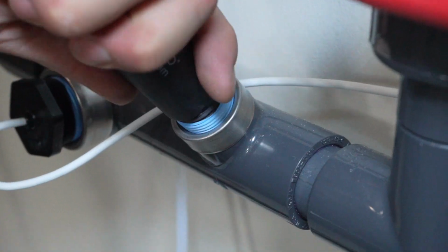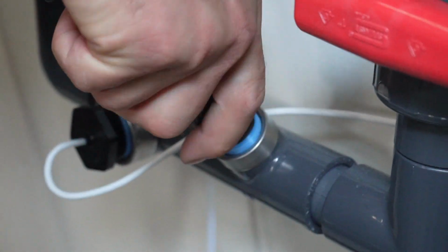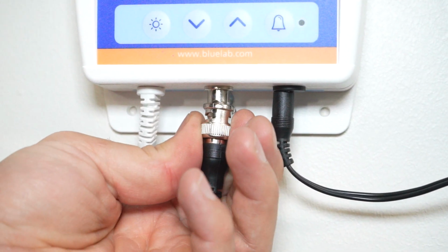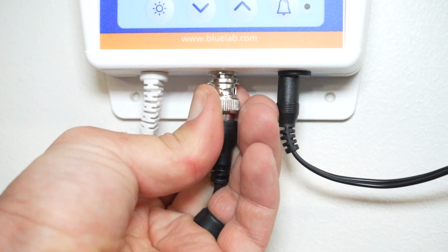The pH probe typically does not require any hand tools for installation. With the wire detached from the monitor, thread the probe into the monitoring loop by hand, and once snug, reattach the cable end into the monitor. Note that the pH probe cannot be left in the monitoring loop without water in the loop. Remember the old saying, if it dries, it dies.